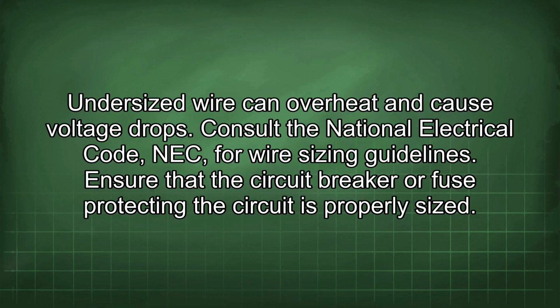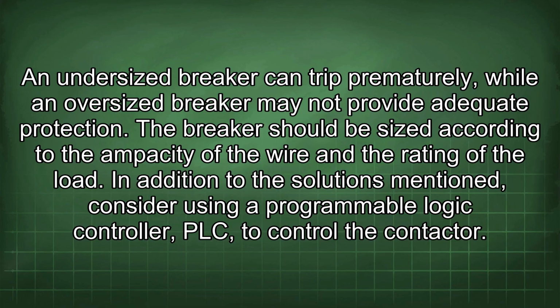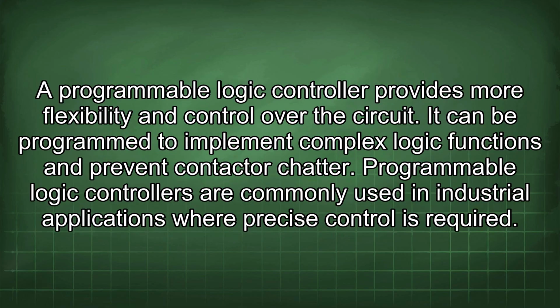Ensure that the circuit breaker or fuse protecting the circuit is properly sized. An undersized breaker can trip prematurely, while an oversized breaker may not provide adequate protection. The breaker should be sized according to the ampacity of the wire and the rating of the load. In addition to the solutions mentioned, consider using a programmable logic controller (PLC) to control the contactor. A programmable logic controller provides more flexibility and control over the circuit. It can be programmed to implement complex logic functions and prevent contactor chatter. Programmable logic controllers are commonly used in industrial applications where precise control is required.